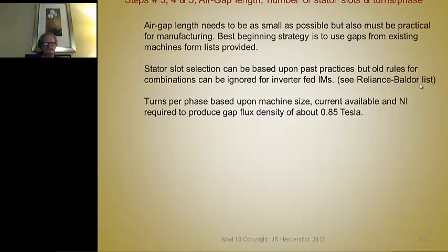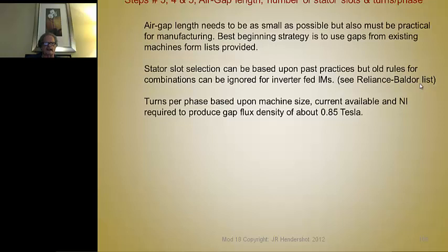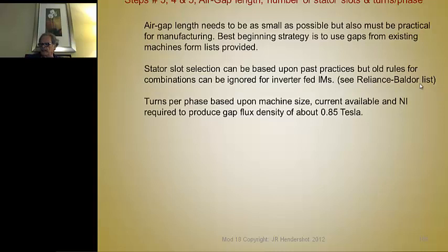For steps three, four, and five, we need to determine the air gap length, the number of stator slots, and the turns per phase. The air gap length should be as small as possible but also practical for manufacturing. You can start by using the air gaps from the list on the preceding slide — that's a very good place to start. Alternatively, if you work for a large company like ABB, you already have typical air gaps versus rotor size data.